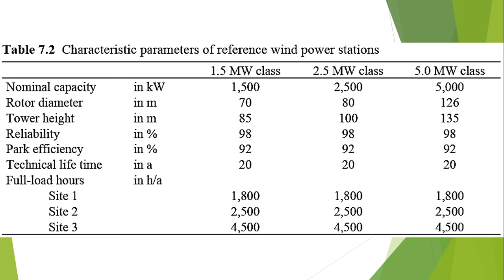The resulting full load hours — that is, the ratio of approximate annual power generation to nominal converter capacity — for various wind converters of the same capacity are illustrated in this table. A generation availability of 98% as the reliability factor and a wind power efficiency of 92% have been assumed to assess the costs incurred by wind power utilization. The variable and fixed costs of the reference plants are mentioned, and the power generation costs are calculated in relation to the respective available wind quantities.